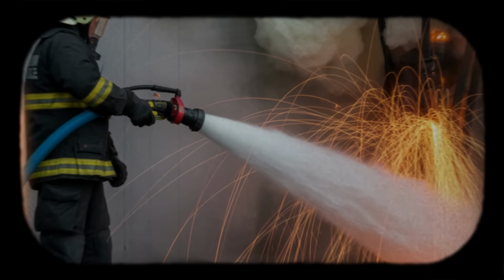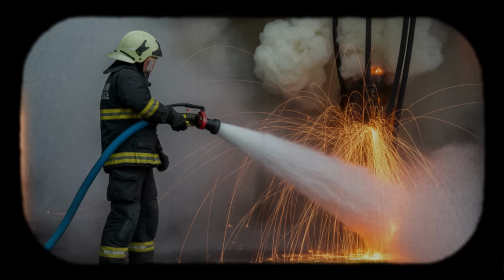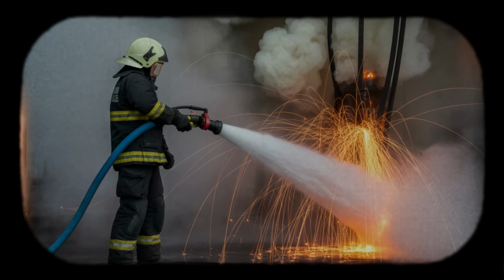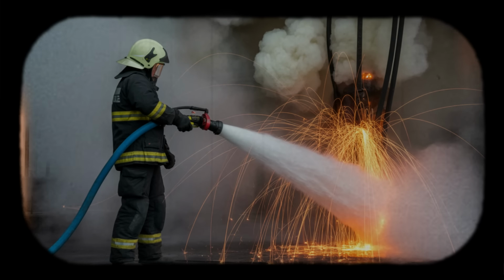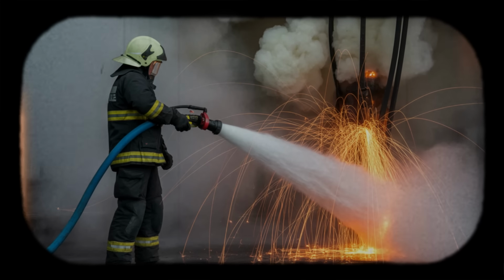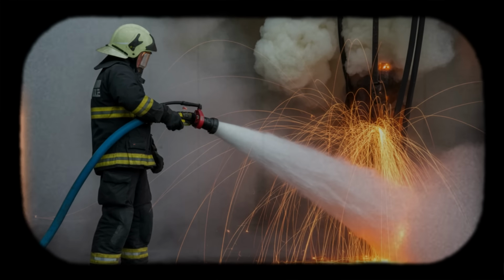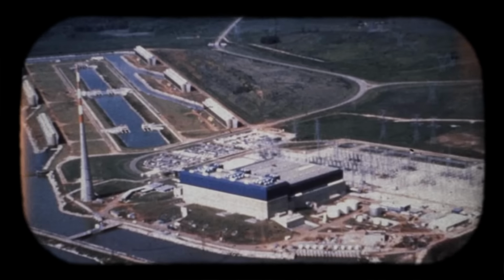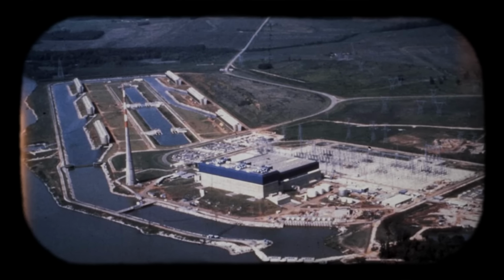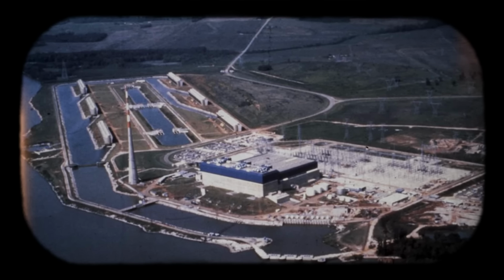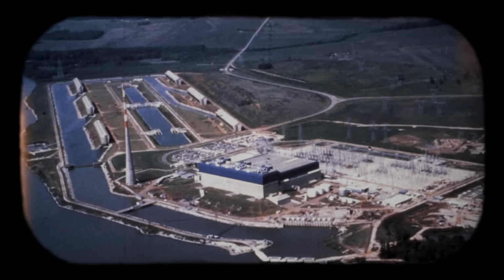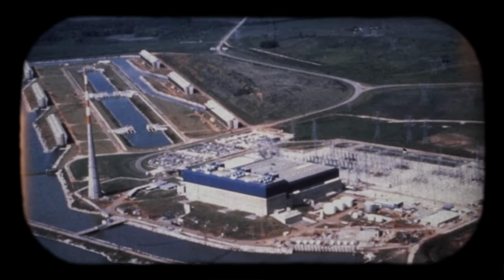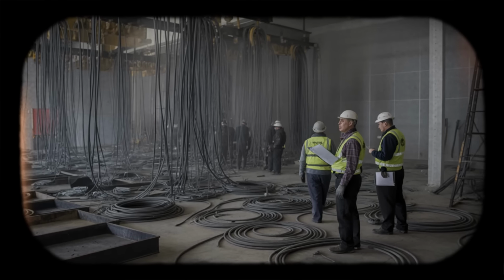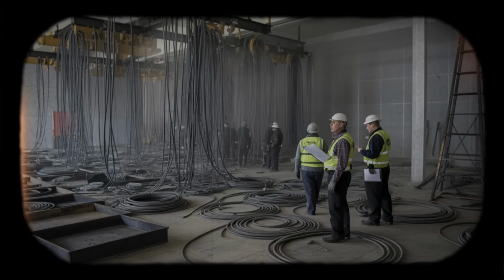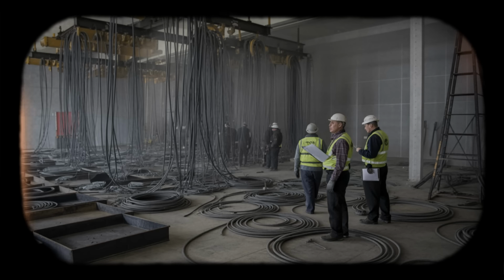The changes affect every aspect of plant design. Cable trays are rerouted. Walls are added to create fire compartments. Coatings are applied to structural steel to prevent heat-induced failure. Emergency lighting systems are upgraded to function during fire conditions. Alternative shutdown panels are installed outside the main control room to provide backup control capability if the control room becomes uninhabitable due to smoke or heat. The work takes years and costs hundreds of millions of dollars across the industry. But the alternative, operating with the vulnerabilities Browns Ferry revealed, is unacceptable. The potential consequences of common mode cable fire affecting multiple safety systems are too severe to ignore.